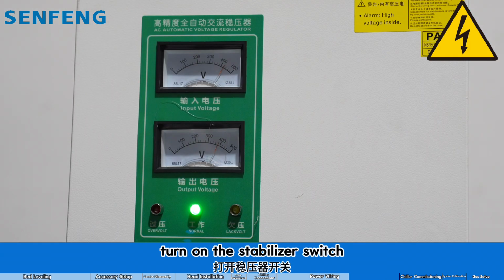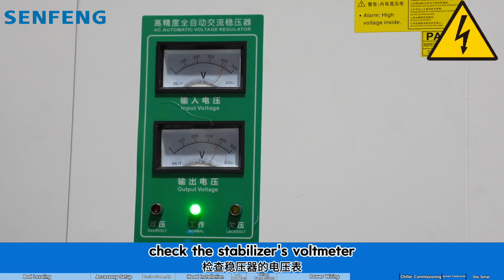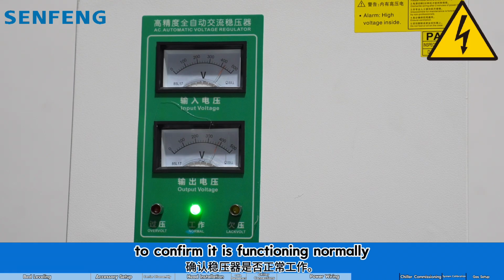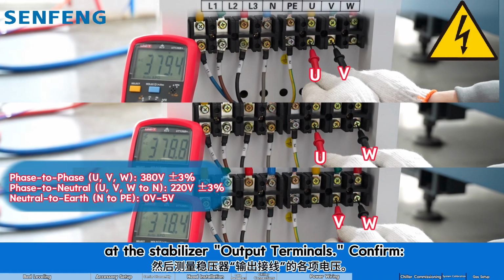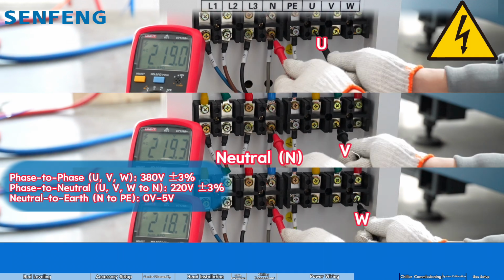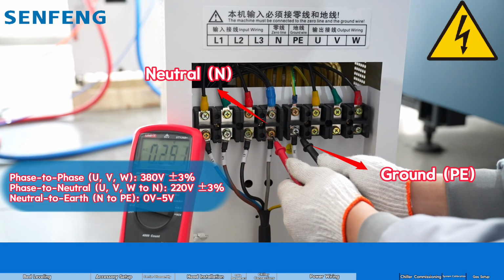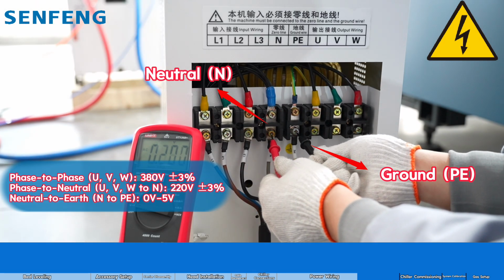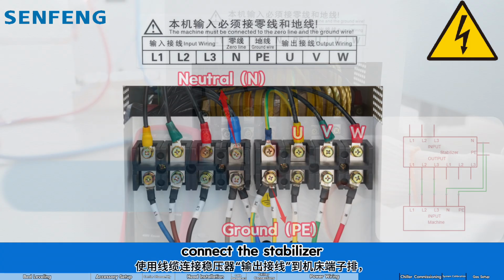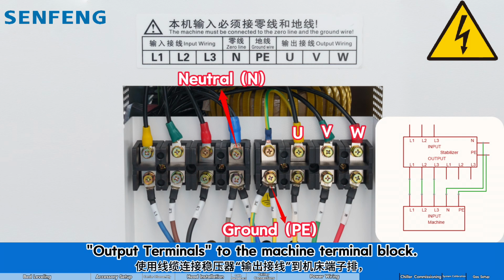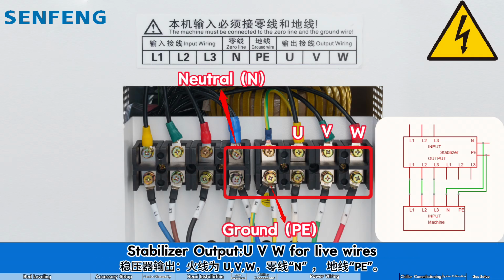Turn on the stabilizer switch. Check the stabilizer's voltmeter to confirm it is functioning normally. Measure the voltages at the stabilizer output terminals. Connect the stabilizer output terminals to the machine terminal block. Stabilizer output U, V, W for live wires, N for neutral, and PE for ground.